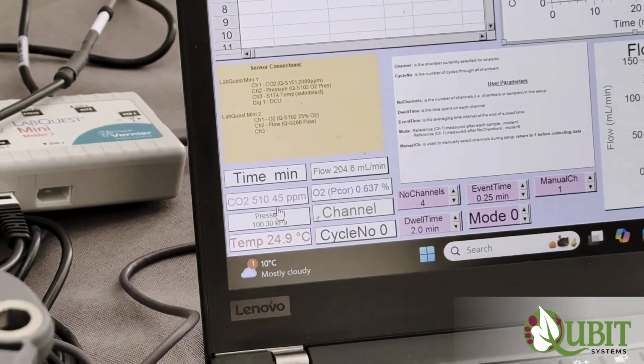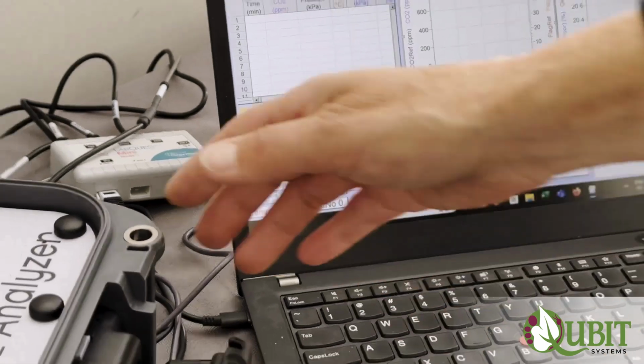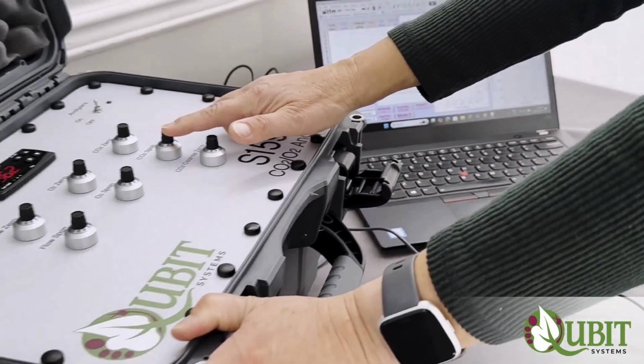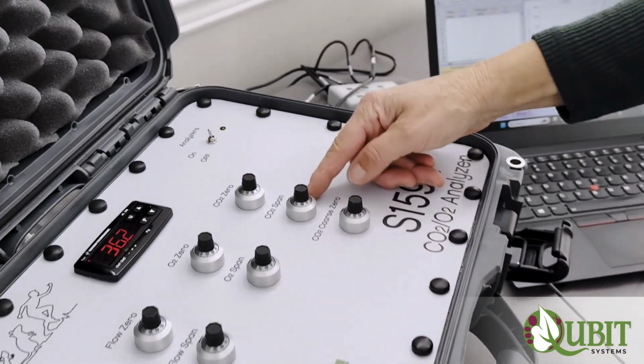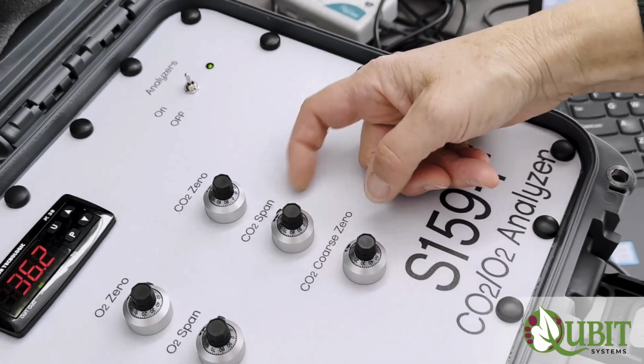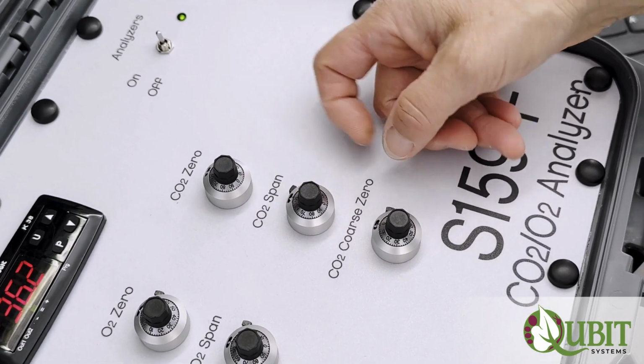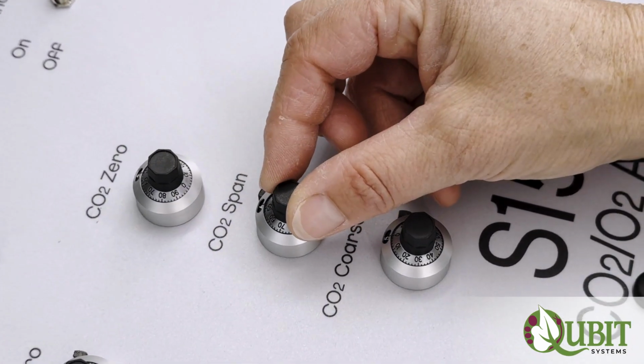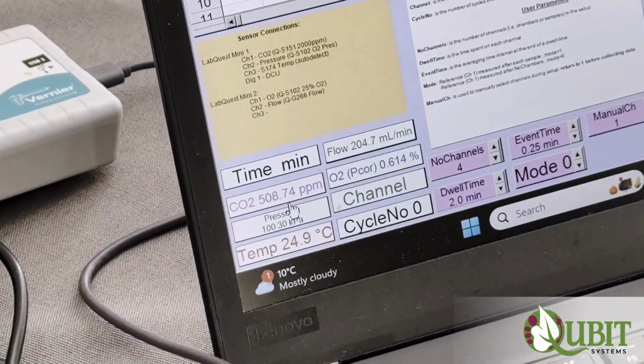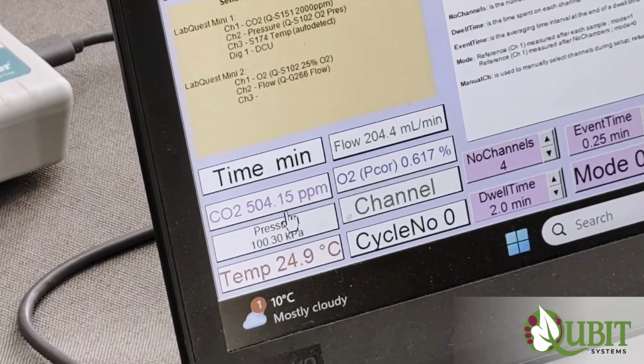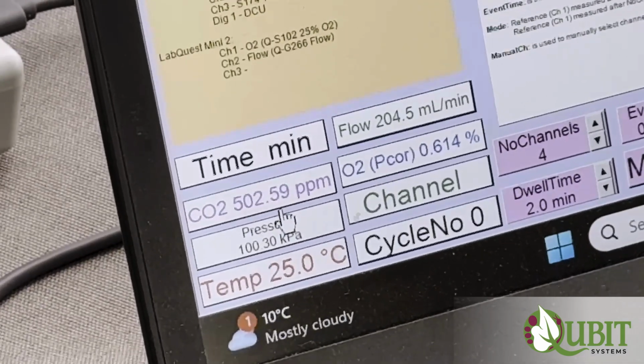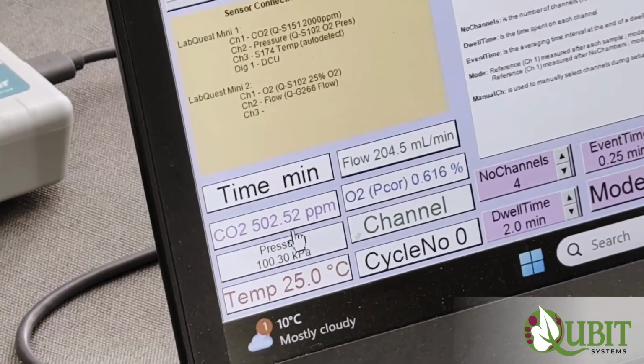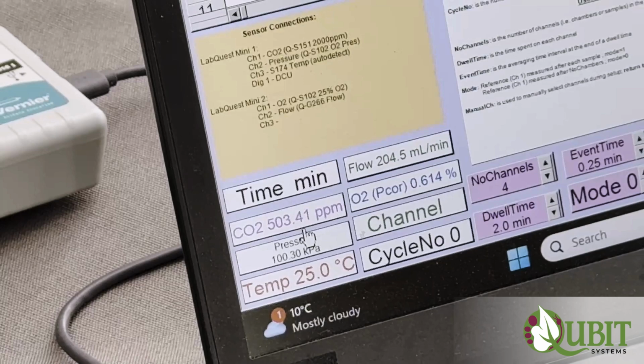What we need to do is we need to reduce that to 505, and we do that with the CO2 span. Again, we have to unlock this knob by pushing the tab up, and then you reduce the reading by turning it anti-clockwise, and if you have to increase it, you turn it clockwise. So 503, 502, I've gone too far.